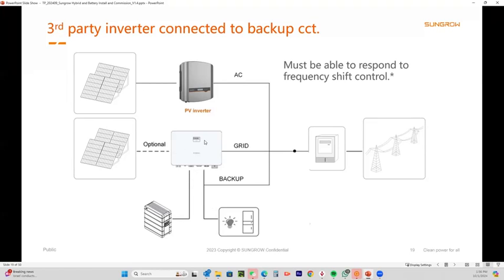It can't produce more power than is being used. It will ramp down, but it will also lift the output frequency to 52 Hertz to shut this other one down as well. Okay, so that is how it controls the other inverter output. Obviously, when there is demand for power, it will drop the frequency back down to 50. This inverter here, after 1 minute, will come back in because it's detecting grid frequency and voltage. Okay, the output voltage will be 230 volts, by the way. And there is a setting, if you are doing this, let us know.